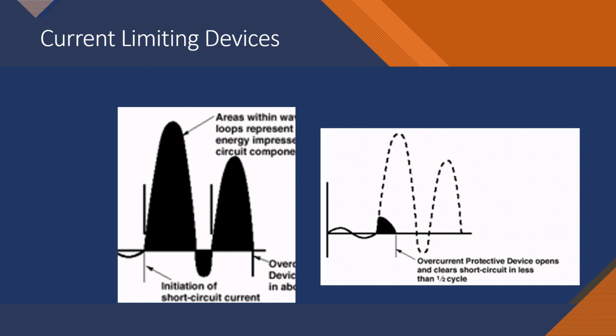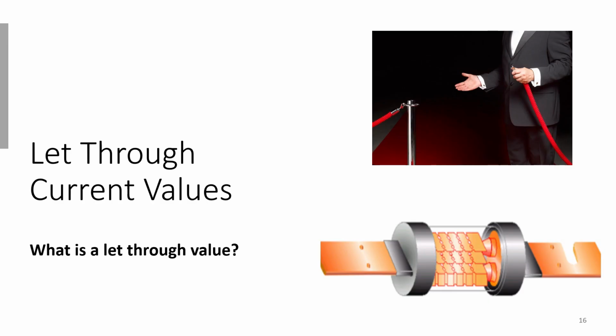We'll often get plans in that say the let-through value of a fuse. Right? So I may have a short circuit current rating of 50,000, but the let-through of my fuse is only 22. So the engineer is going to tell me, hey, it's okay to put a breaker in that's only rated at 22, even though I have a short circuit current that is much higher. Okay, and that's partially true, like many things in the National Electric Code. It's just partially true.